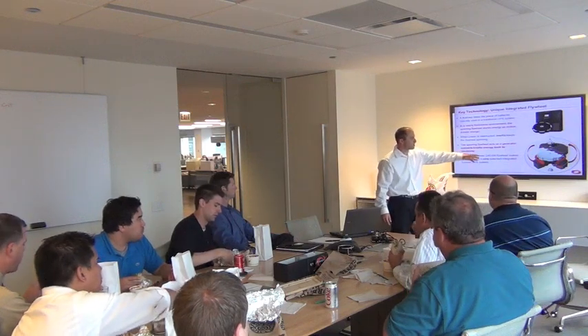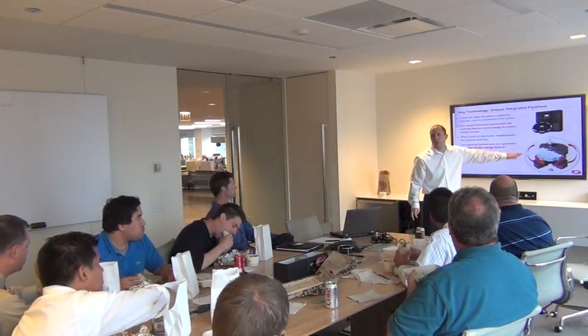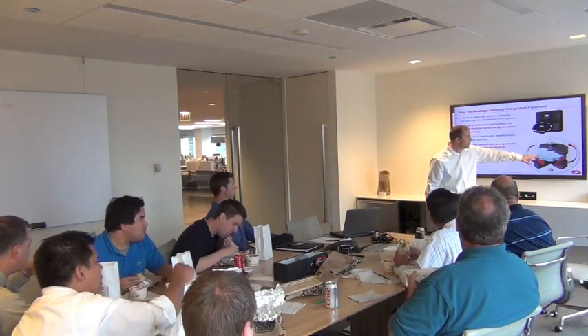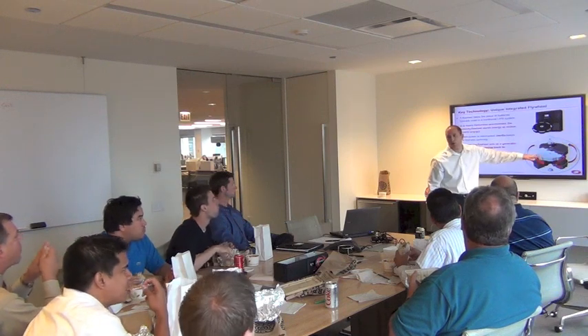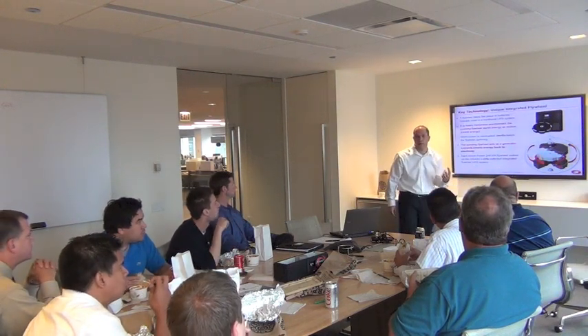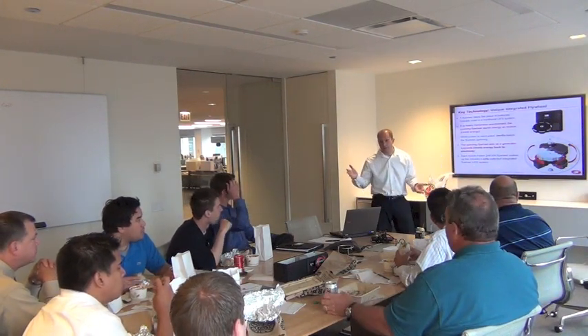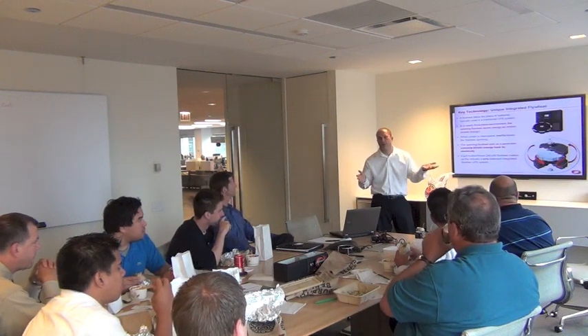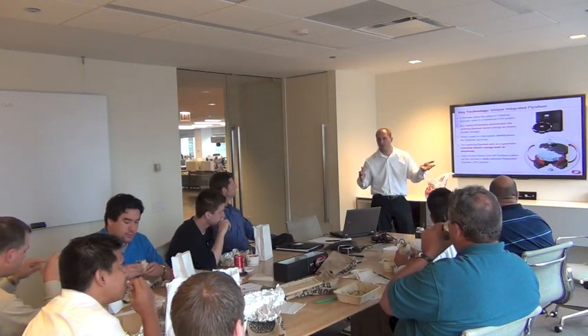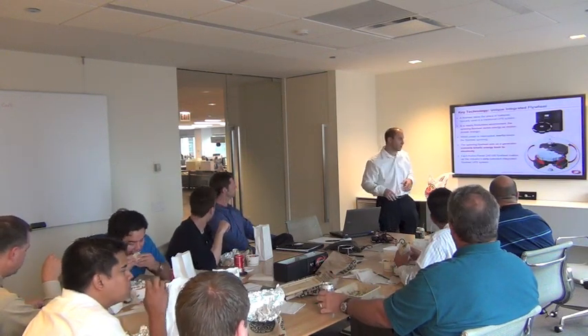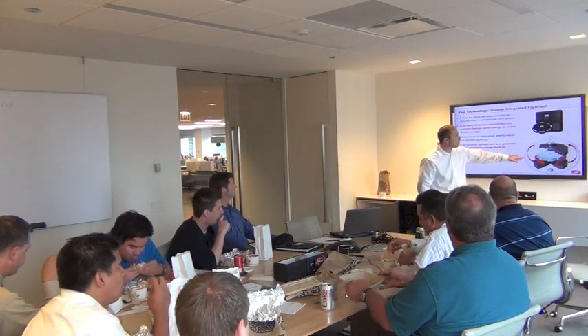Basically, the heart of our business is a 250 kilowatt flywheel. It's basically composed of a 4340 steel rotor that spins at 7,700 RPMs. In the event of an outage, the UPS is going to go into discharge. Once your generator comes up to speed and voltage, we're going to synchronize with the generator, and we're going to walk the load onto the generator. So again, it's a 250 kilowatt wheel.